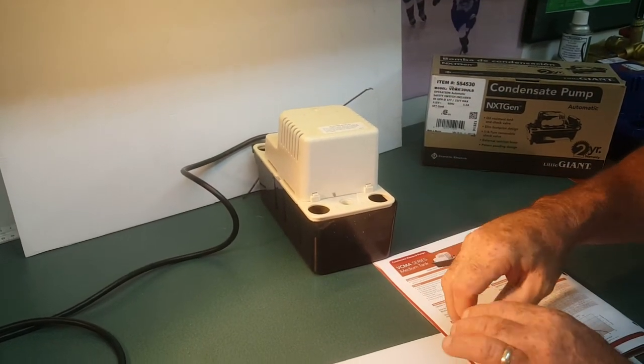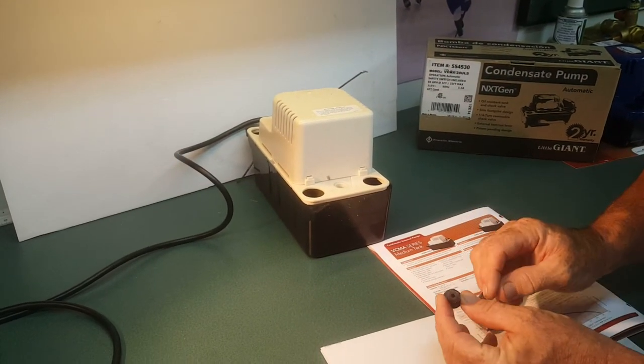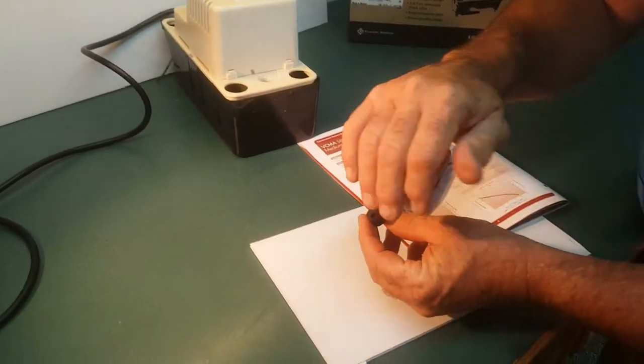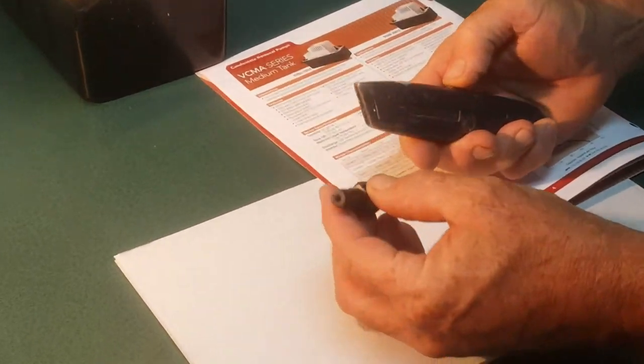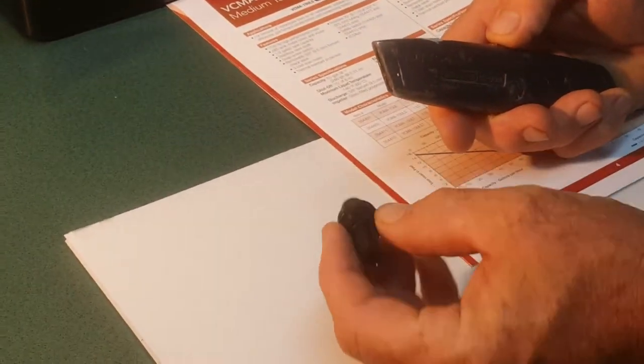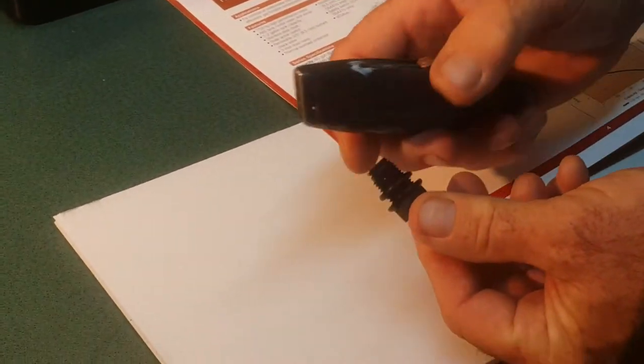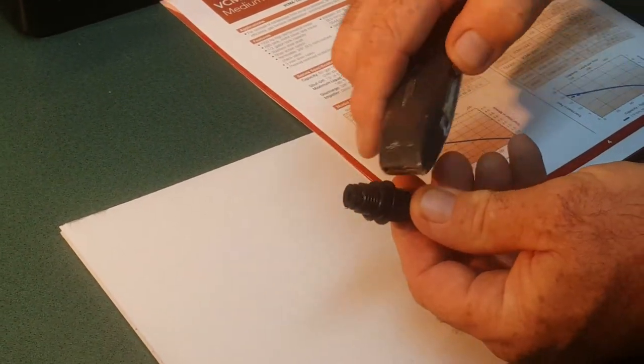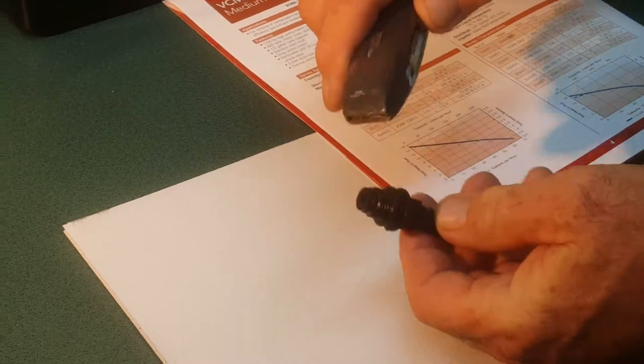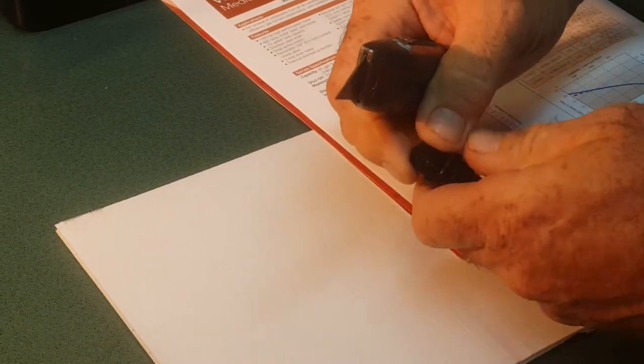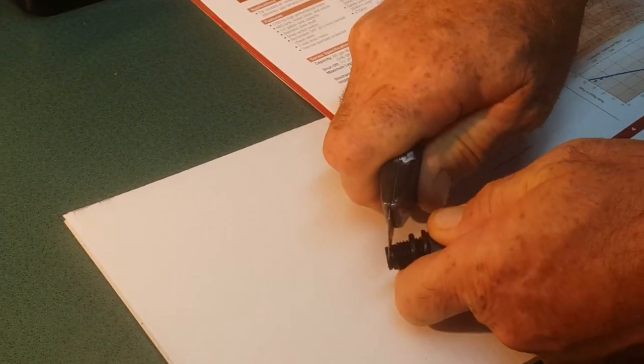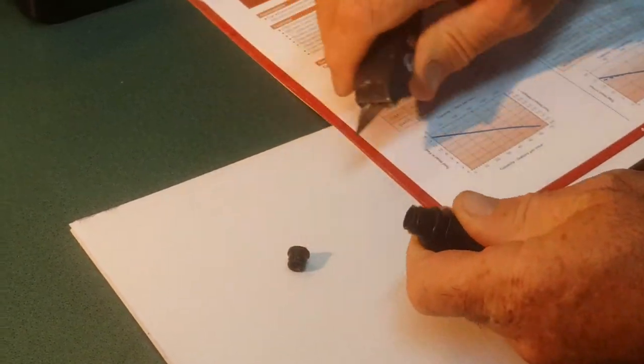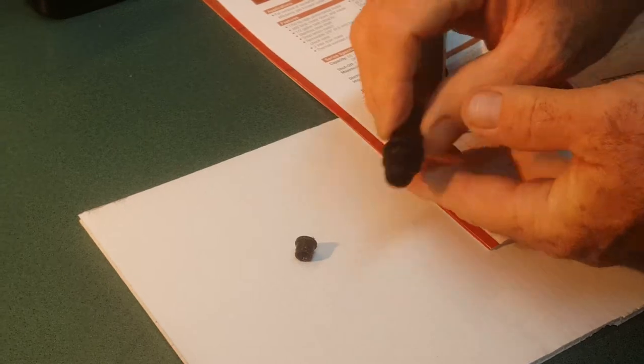The dirt was blocking the hole. So what you can do with these check valves is on the entry hole here, that's just a plug that you can pop off. And when you do that, then you can knock the ball out of there.